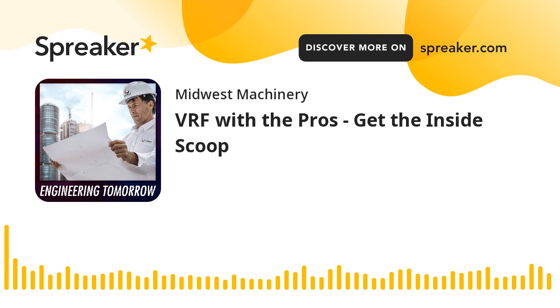What do you typically see in terms of installation? Are most of these installations doing simultaneous heating and cooling? Is it changing over time? How is that trend going? So the really nice thing about VRF systems is that they're super flexible. The ideal installation isn't limited to one instance or application. I've seen VRF systems applied to Class A office buildings, universities and institutional work, hotel retrofits, hospitality, even religious buildings, great for retrofitting areas that may or may not need heating or cooling.